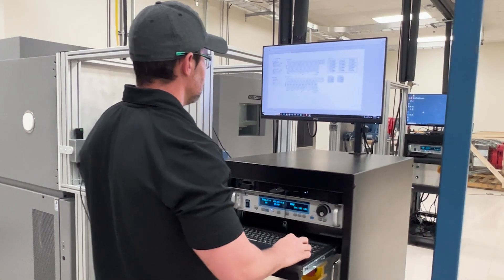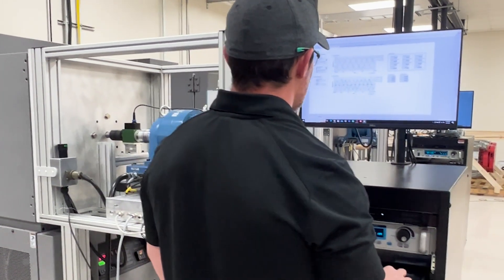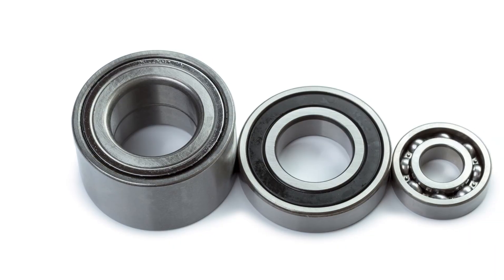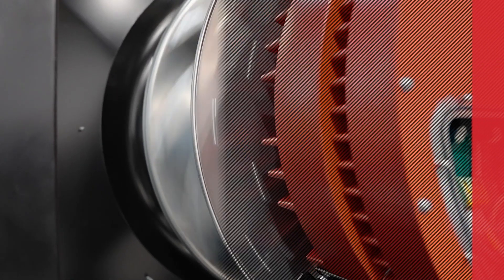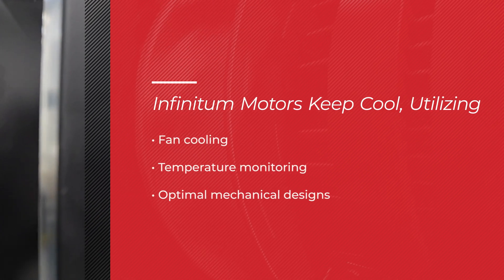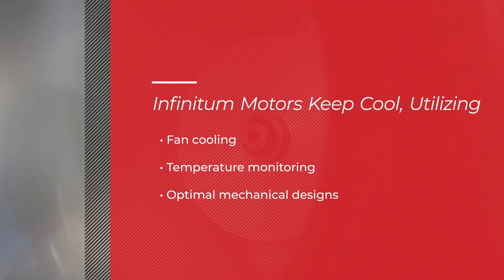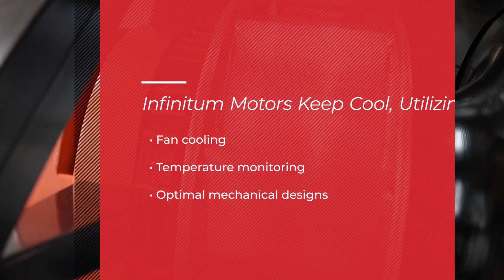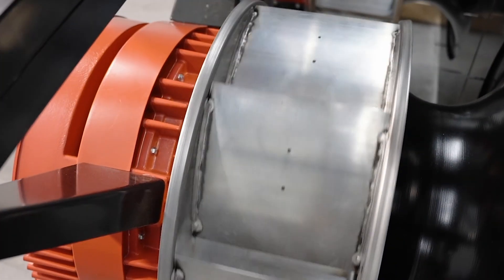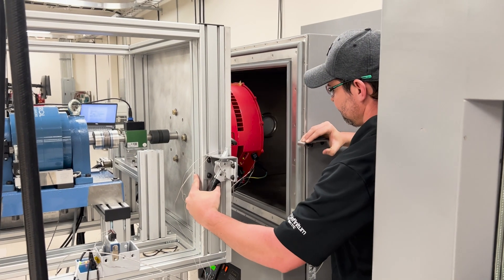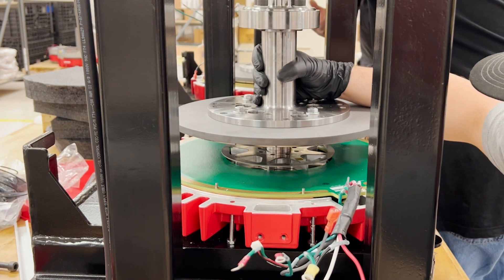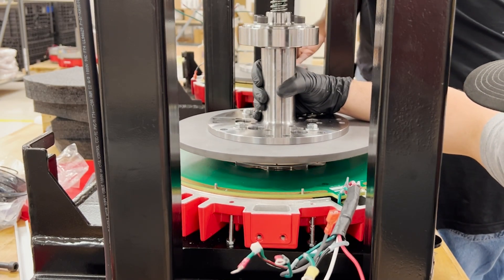Infinitum goes beyond to take preventive measures to mitigate bearing failure throughout the design process. Infinitum uses steel bearings and steel races on all of our motors. Infinitum motors are kept cool through fan cooling, continuously monitoring motor thermals to prevent over-temperature conditions, and optimal mechanical designs to pull heat out of the motor. We design and select our motor bearings with success in mind, using a hybrid 6200 series steel bearing or equivalent. We utilize grounding rings and shaft brushes to eliminate shaft voltages that would damage bearings.